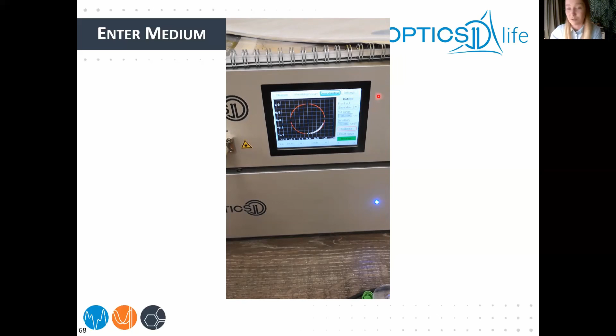So the easiest is to bring the probe out of the medium and bring it back in. Run liquid, pre-wet the probe, and it should go back to normal, and your signal will come back to where it was. So that's what I meant by this signal is basically your eyes. You know exactly what's happening. You don't need to even look at the probe to see what's really there.